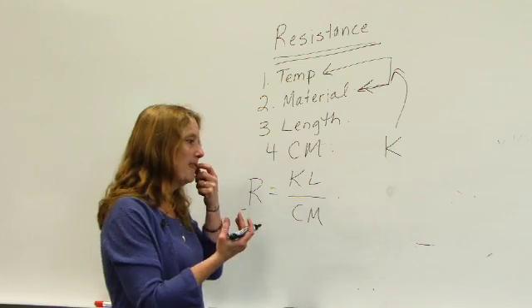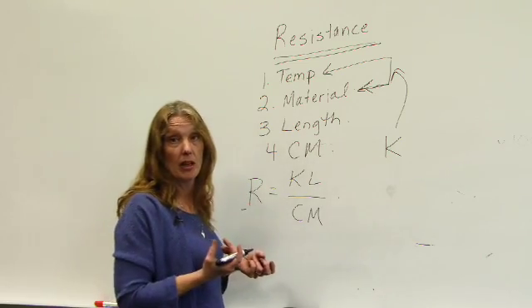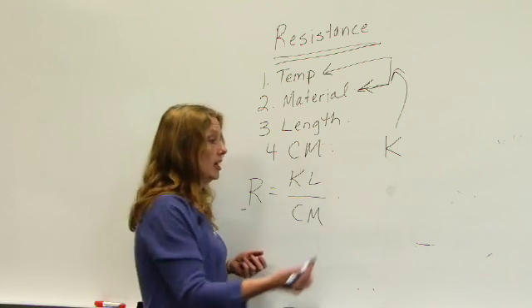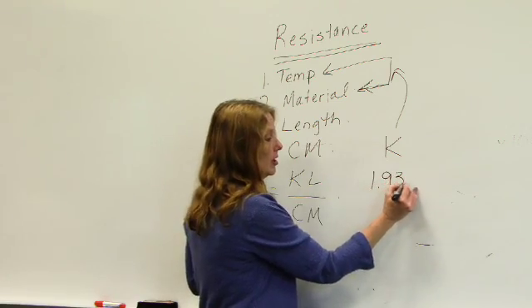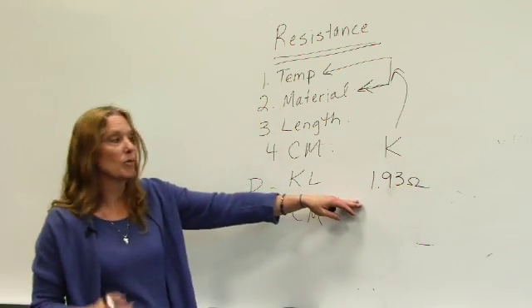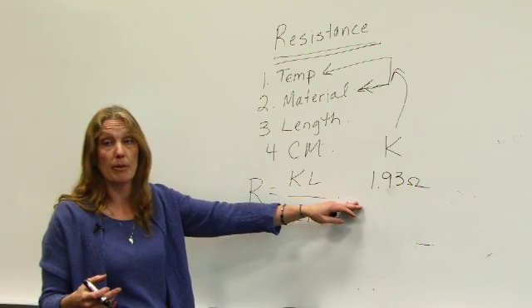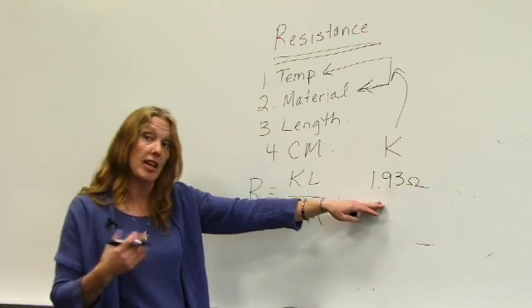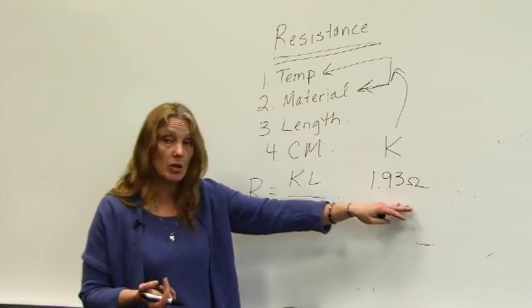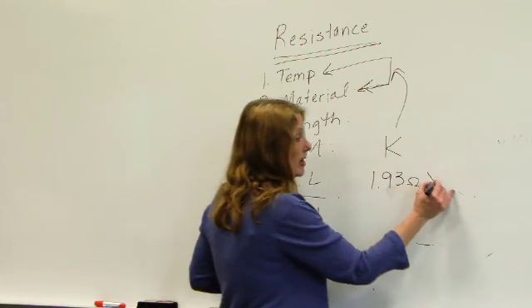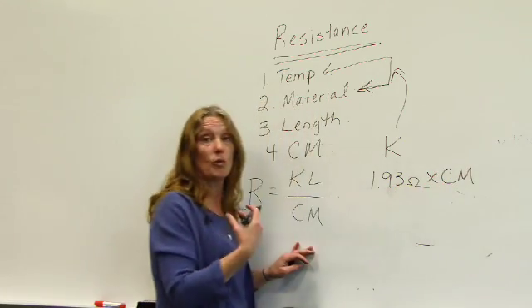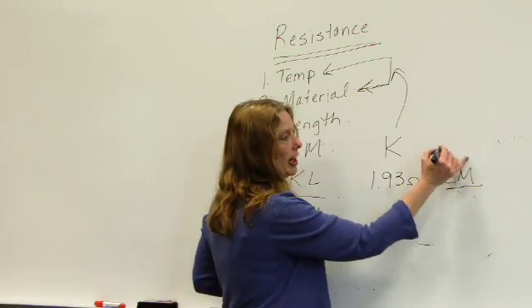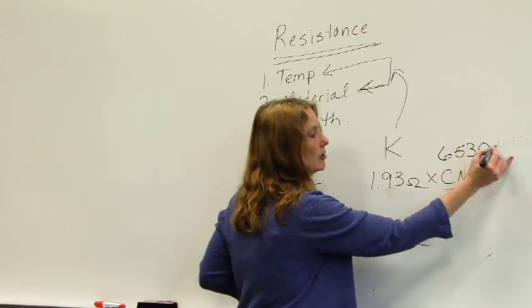So let's think about a K value using a number 12 copper conductor. The ohms per thousand feet of a copper conductor, a number 12 gauge, is 1.93 ohms. So that tells me I get 1.93 ohms per thousand feet of a number 12 gauge copper conductor. So to calculate K here, I take this value and that is at 86 degrees Fahrenheit, and I'm going to multiply it times my circular mill area of that number 12 gauge wire. If I look at a number 12 gauge copper wire, I realize that the circular mill area is 6530 circular mills.